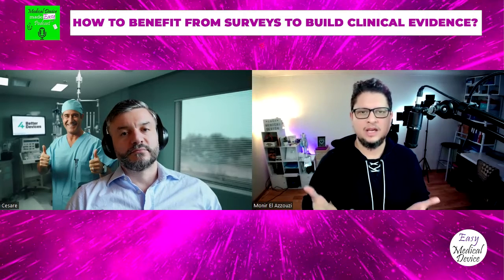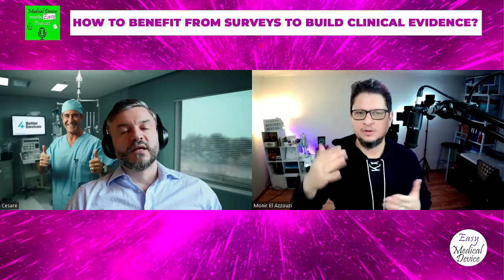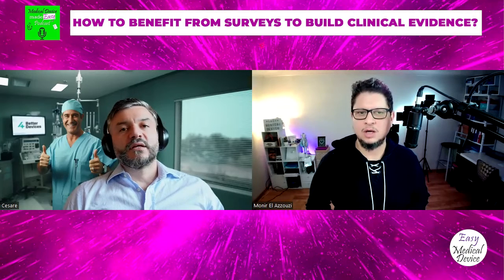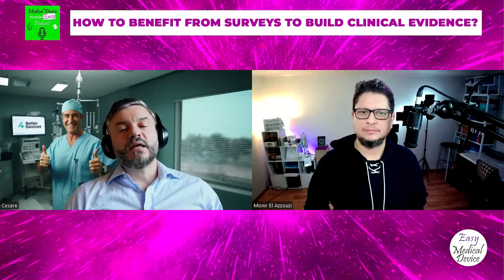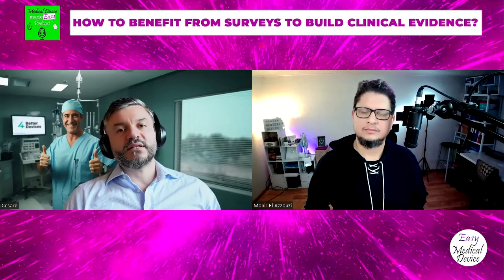Notified bodies, do they care about those levels, or which level you are choosing or how you are making that? Yeah. It's important to be able to classify the clinical evidence in levels, because especially for class 3 devices, the guidance says you have to have at least level 4 and above. So it is quite important.